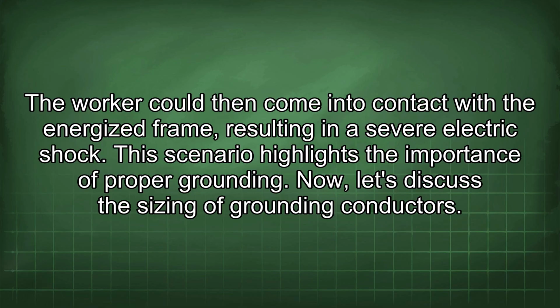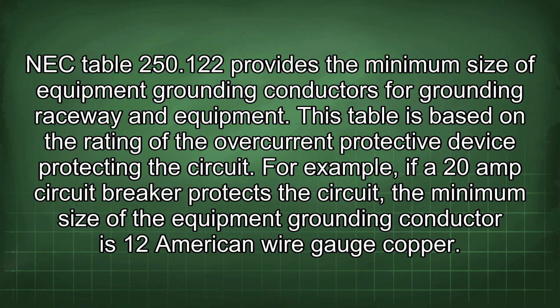Now, let's discuss the sizing of grounding conductors. NEC Table 250.122 provides the minimum size of equipment grounding conductors for grounding raceway and equipment. This table is based on the rating of the overcurrent protective device protecting the circuit. For example, if a 20-amp circuit breaker protects the circuit, the minimum size of the equipment grounding conductor is 12 American wire gauge copper.